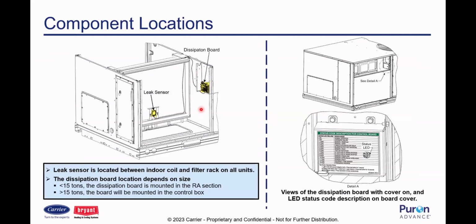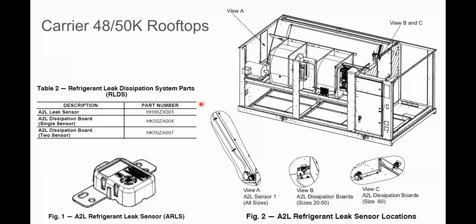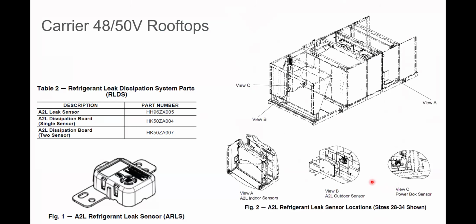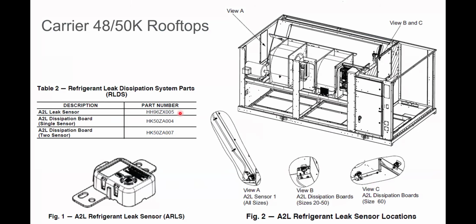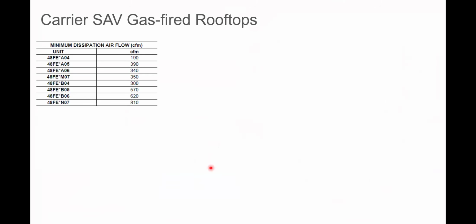You have an IGC board, contactors, transformer. You got the EcoBlue speed control board. You got economizer control. Like you run out of space. There's no more space to shove another board in there. So they're sticking it in the return air now. If it's bigger than 15 tons, then the cabinet's bigger, so they got more room for more boards in there. So you'll find it in the control enclosure then. As mentioned, some of the rooftop units have 2 or 3 sensors in there. There'll be a not awesome drawing showing you where this stuff is supposed to be located to try to help you find it, right, on any given rooftop unit. And there's the part numbers for the boards and sensors if you're trying to hunt them down.